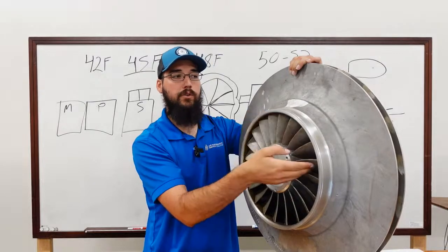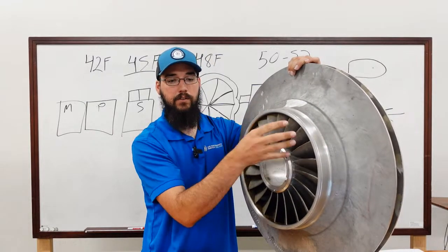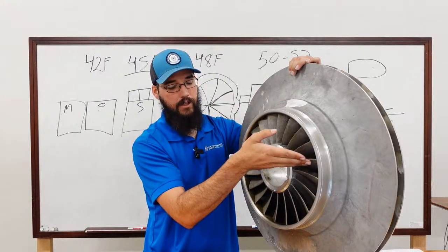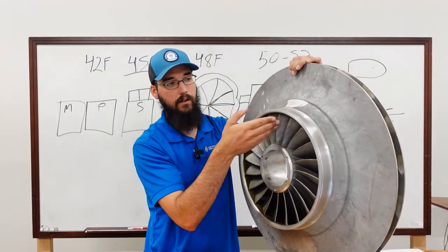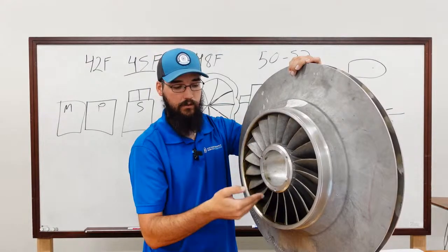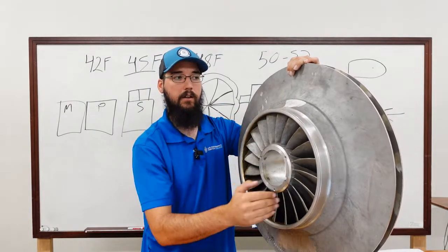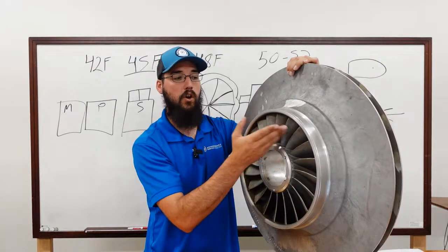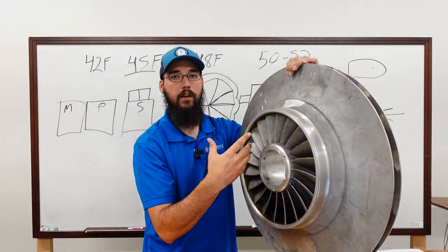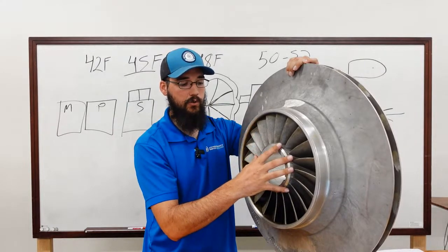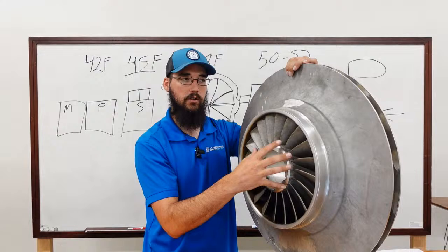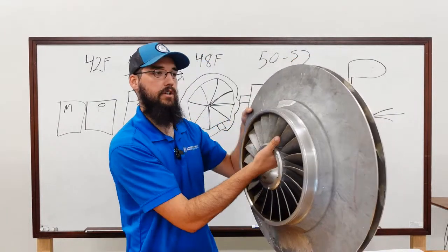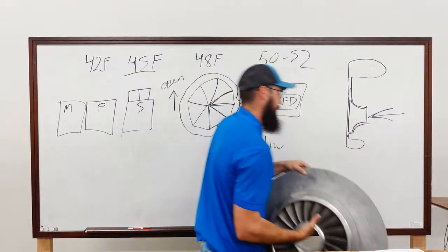Instead of just one or two vanes stopping flow and stalling out, you actually end up having the vanes rotate, and it will rotate around vane to vane in a continuous pattern, and slowly more and more vanes will continue to stall and rotate around. And with stall, you can actually hear it beginning to happen before the surge takes place. That's if it's not an extreme case.